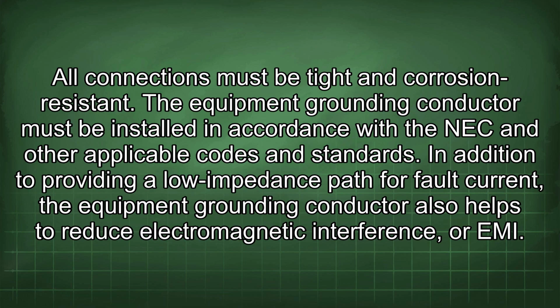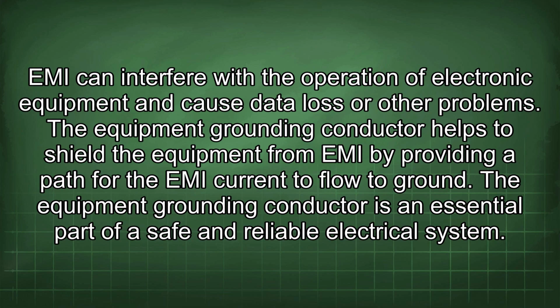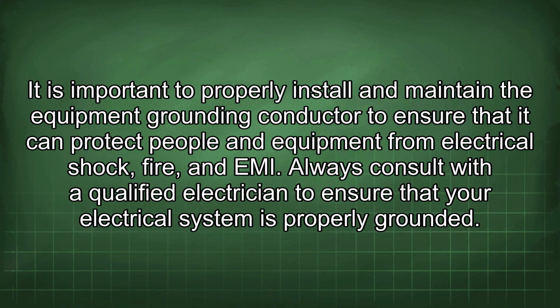In addition to providing a low impedance path for fault current, the equipment grounding conductor also helps to reduce electromagnetic interference, or EMI. EMI can interfere with the operation of electronic equipment and cause data loss or other problems. The equipment grounding conductor helps to shield the equipment from EMI by providing a path for the EMI current to flow to ground. The equipment grounding conductor is an essential part of a safe and reliable electrical system. It is important to properly install and maintain the equipment grounding conductor to ensure that it can protect people and equipment from electrical shock, fire, and EMI.